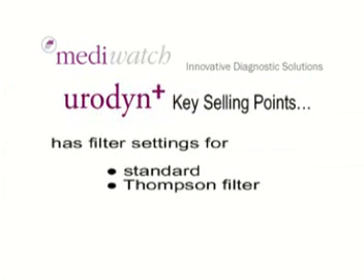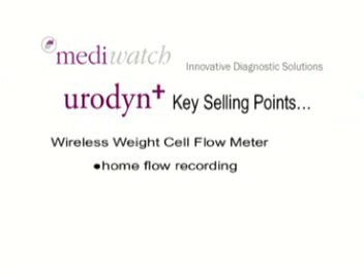Urodyn Plus has a number of configurations: flow timeout, scaling, number of print copies, default gender, and more. Urodyn Plus offers nomograms — Siroky and Liverpool. Urodyn Plus has filter settings for standard and Thompson filters. And the wireless weight cell flow meter can be used for home flow recording.